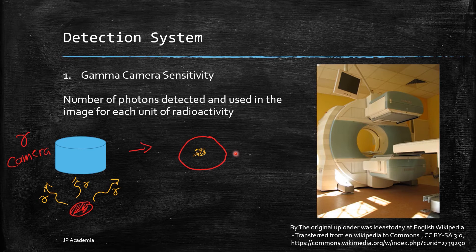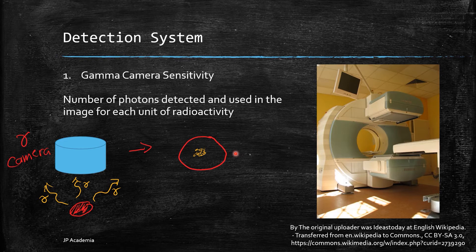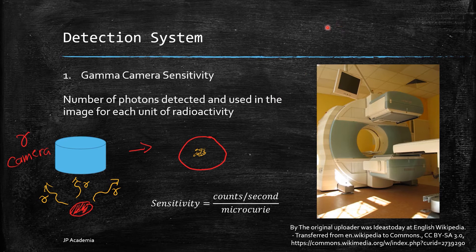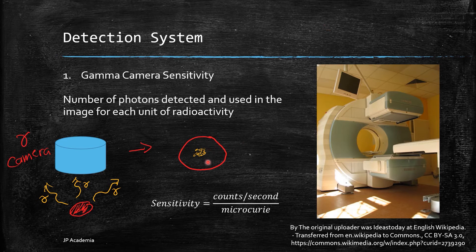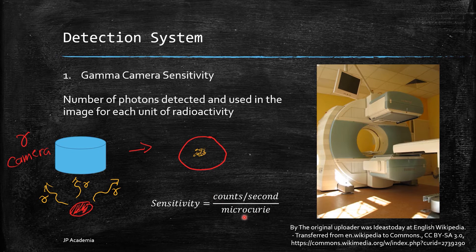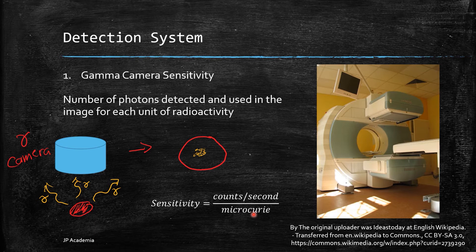However, small fraction of this photon emission are only utilized in the image formation. The sensitivity of a gamma camera is expressed as the number of photons detected and used in the image for each unit of radioactivity, or in terms of microcurie. Camera sensitivities generally range from 100 to 1000 cps or counts per second over microcurie.